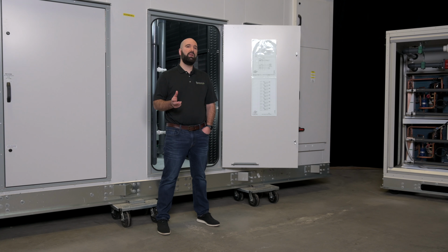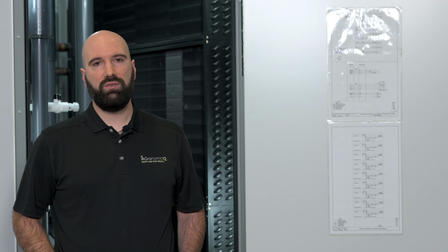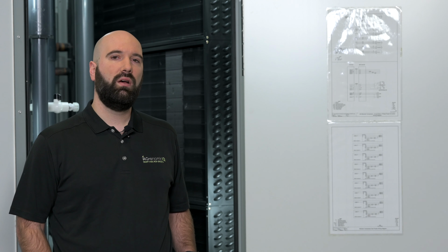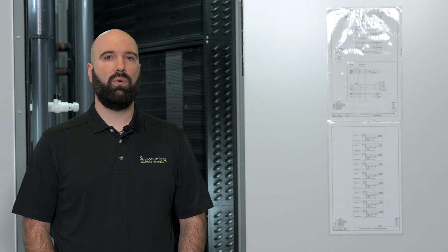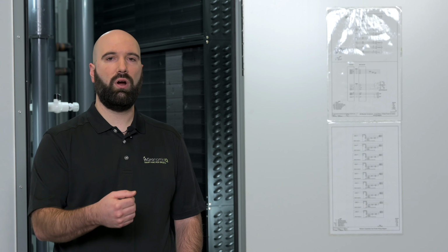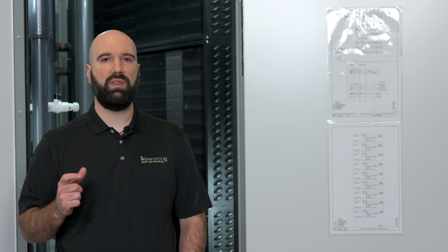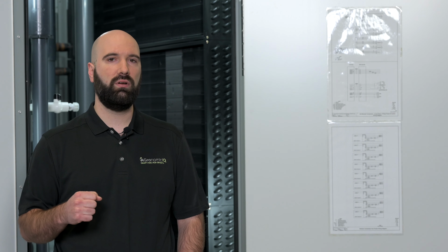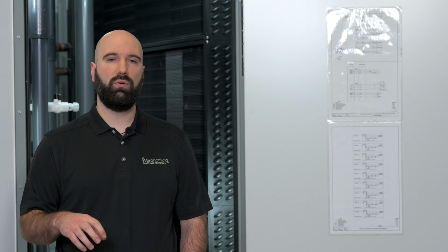And as a result of humidity being relative to temperature, by achieving a tight temperature control, we can very tightly control relative humidity. One of the other things you'll see on this door right behind me are electrical diagrams for this compartment. And these are inside the door for every compartment. And it's another thing that we do just to allow our equipment to be that much more serviceable, that much easier to work on by your local mechanical contractor, by our service techs and by your maintenance guy on site. Let's take a look at the pods.